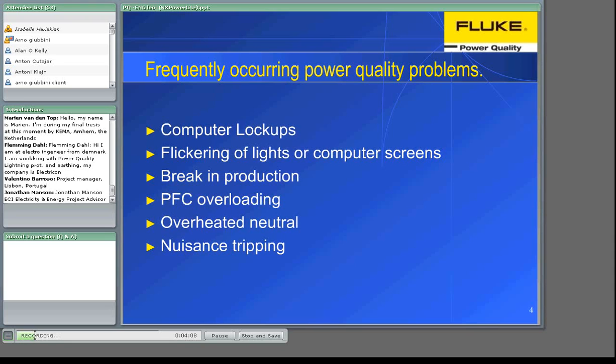Break in production. In continuous process operation, a short interruption can disrupt the synchronization of the machinery. A typical example is the paper making industry, where the cleanup operation is long and expensive. Power factor correction. It is known that the impedance of capacitor banks reduces as frequency rises. Capacitors are therefore likely to carry quite high harmonic currents and damage can result. Harmonic frequencies can coincide with the resonant frequencies of a circuit, creating excessive current leading to a failure.